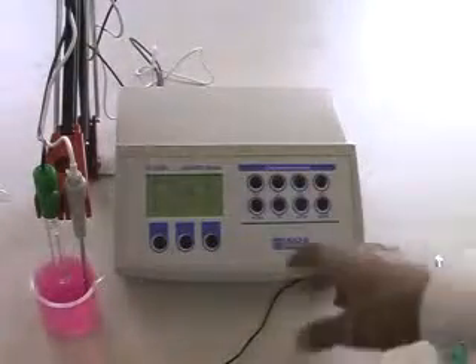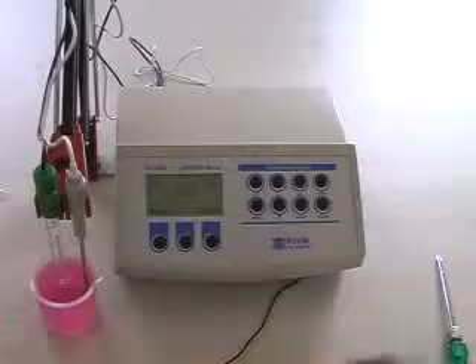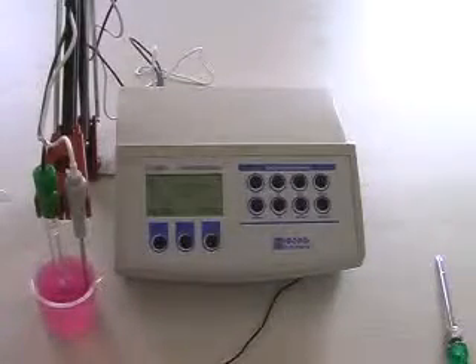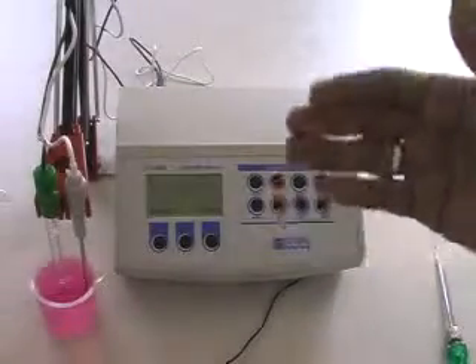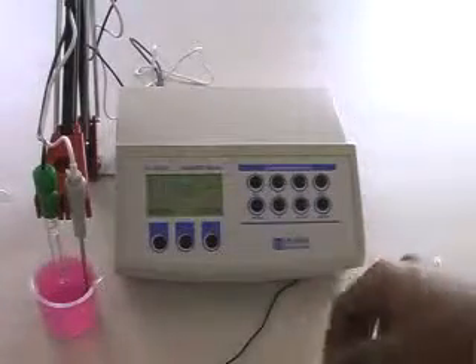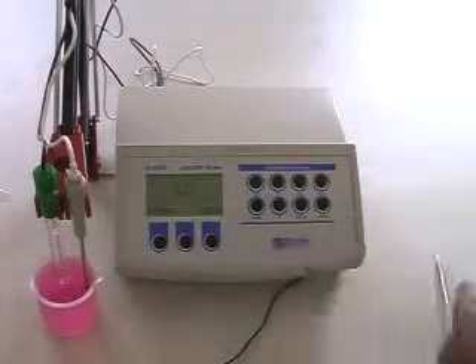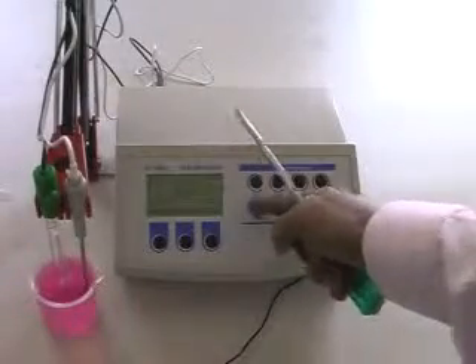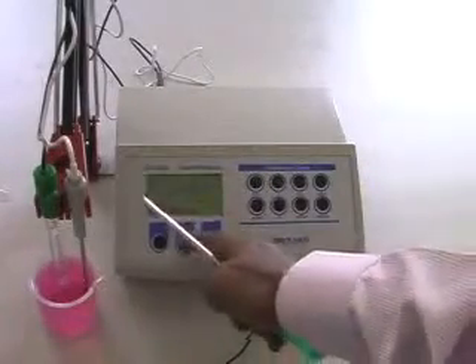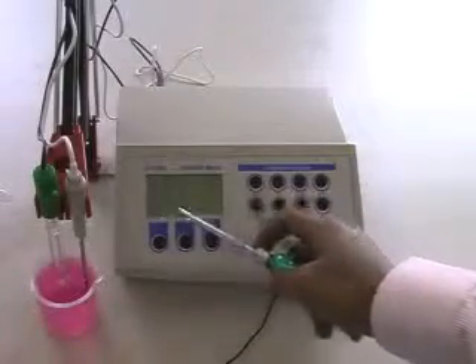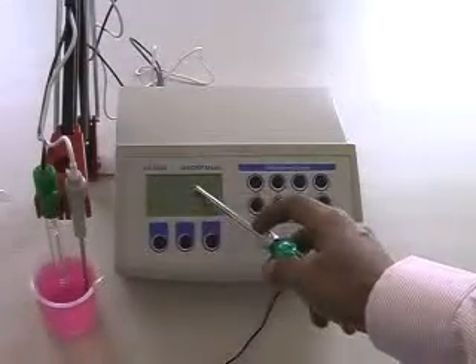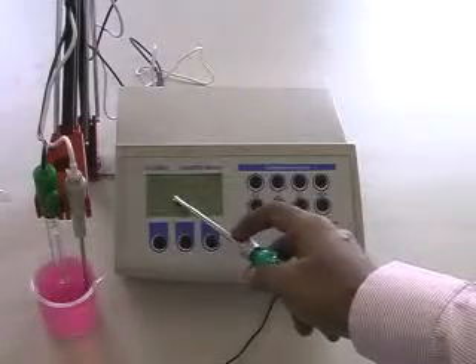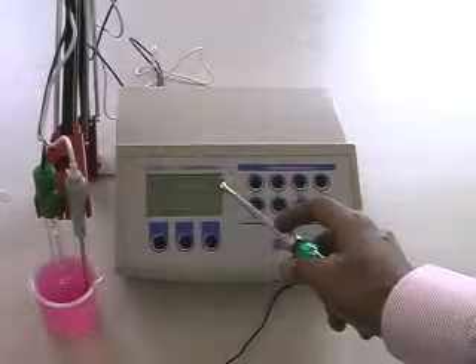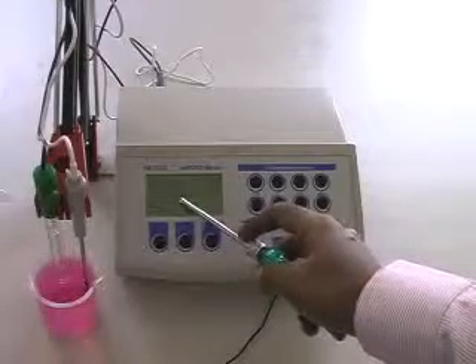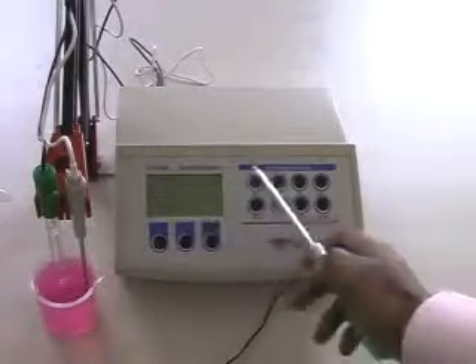If you don't want to calibrate your meter for 5 points, then you have to just press escape. So we have already exited the calibration mode, and now your calibration is saved. If you want to see your calibration, then you have to go to the GLP mode. For the GLP mode, just press menu and hit the GLP button. So see, this is the GLP data. Your instrument is calibrated on 5th of April. This is the time, and this is the first point, second point, and this is your slope and offset and the electrode condition.